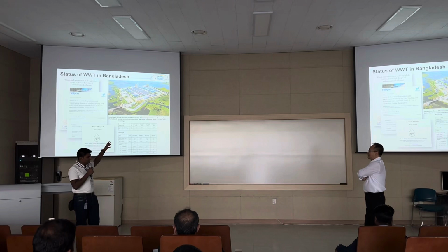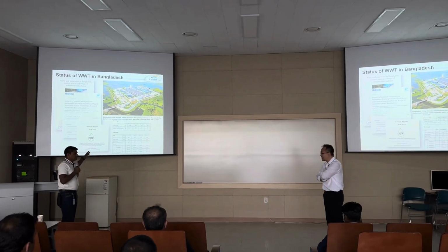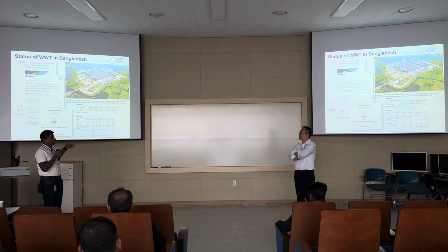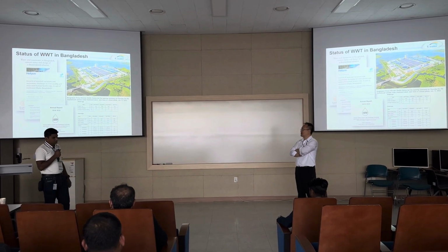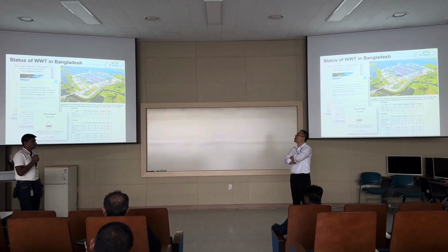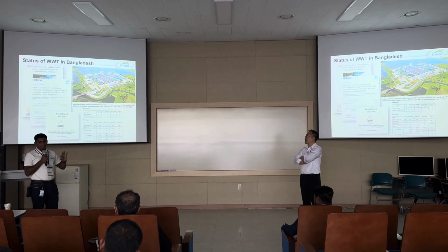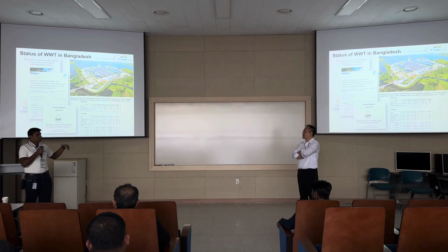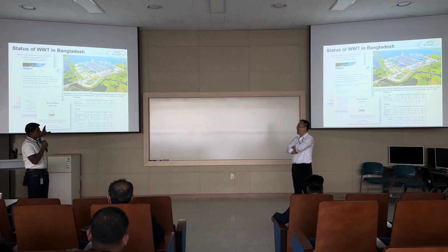As you can see, this is the Tashikandi sewage treatment plant. It has a capacity of 500 million liters per day, and the threshold or design value is 600 MLD. In the treatment capacity, the treatment plant has 3 components. First, the sewage lifting station, where the incoming sewage is lifted first, and then we have 5 kilometers of dual pipelines that convey the sewage to this treatment plant. This is the third portion.